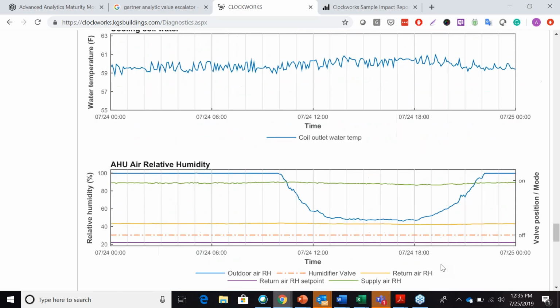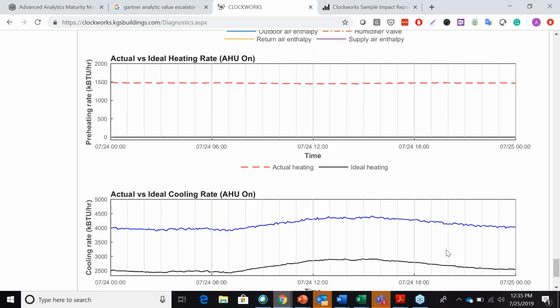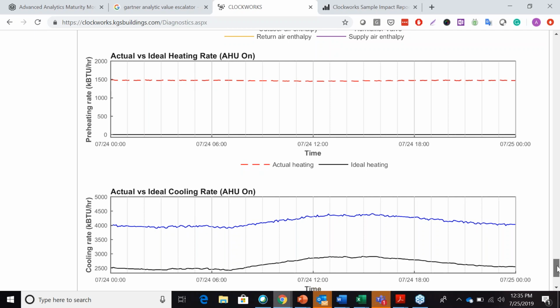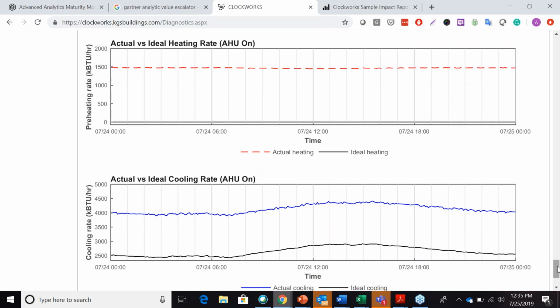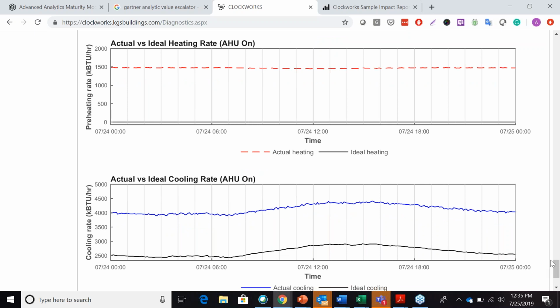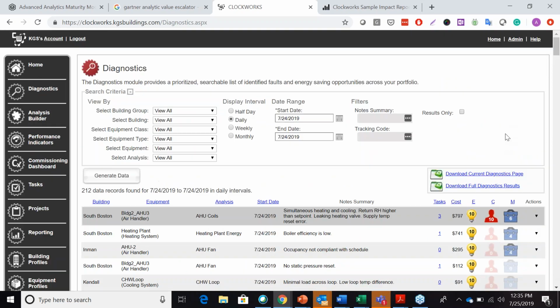And then again, for the energy folks, actually quantifying the actual versus the ideal heating rate and the actual versus the ideal cooling rate. In other words, how much heat should you be using to meet your supply air temperature, and how much heat are you using, and likewise on the cooling side. And that's how the energy calculations are actually done here in terms of the measurement and verification. So I jumped in a little bit of detail there.